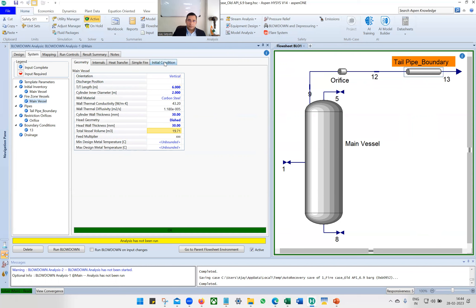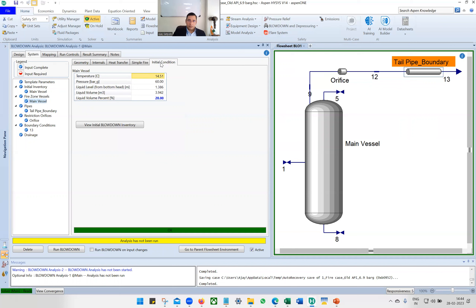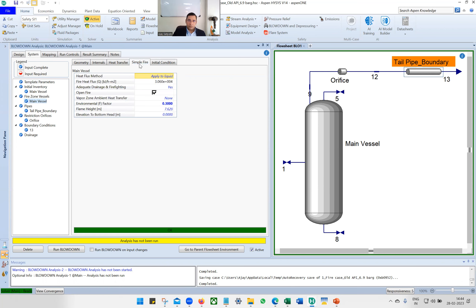Next is initial conditions — set 20% liquid level. Then go to Simple Fire. This vessel has insulation, so the environment factor is 0.3.